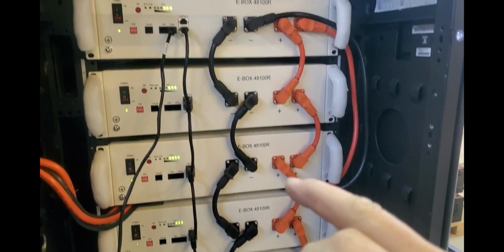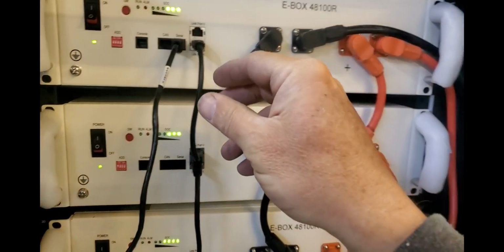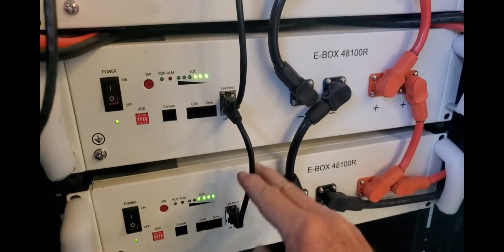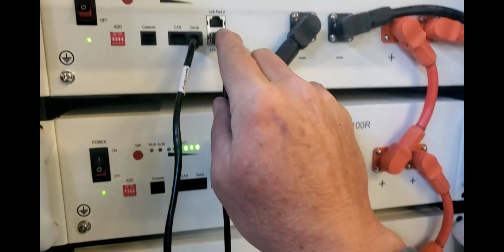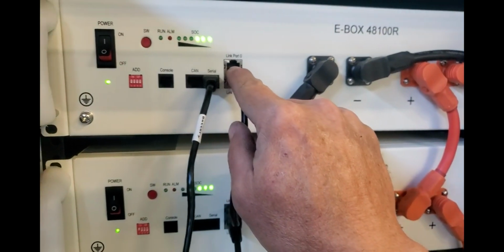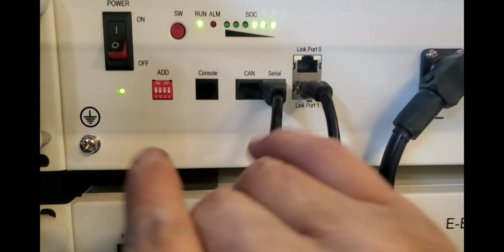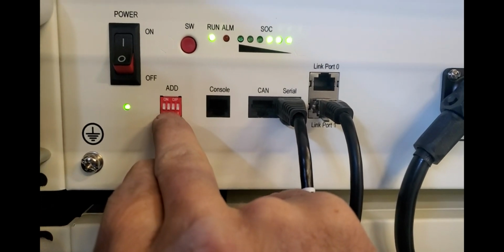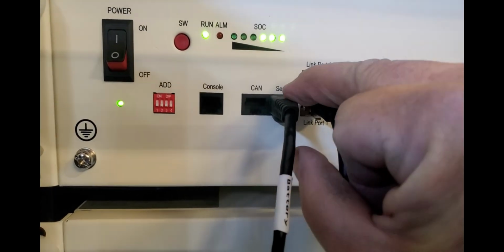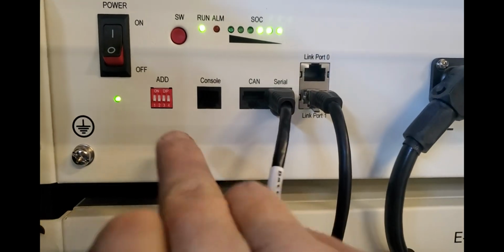Now, this is how we communicate, connecting these guys up starting from the bottom. The one that's open at the top is the master. Now, the addresses are programmed as follows. The top one will be address 0, and we'll notice we use the serial port output for MPP Solar. First one is 0, the second one is 1.